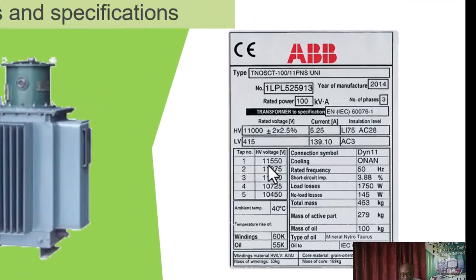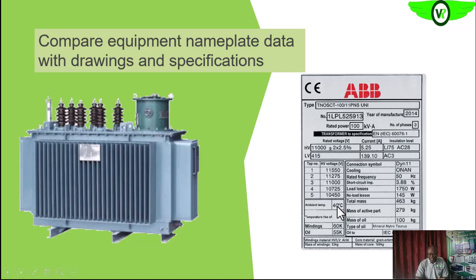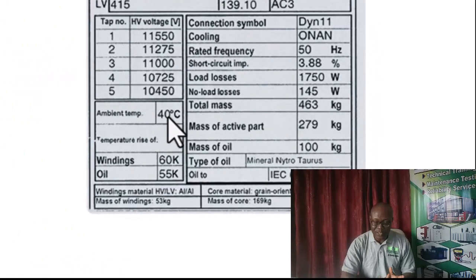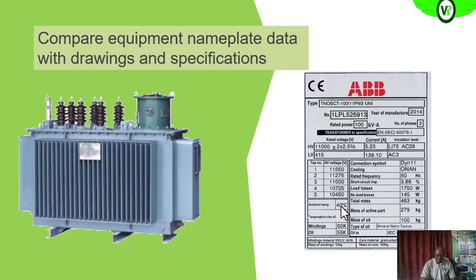Basically, we'll look at the input voltage, that is the high voltage side, and then the output voltage. If it matches what was requested, fine. And then the power rating; those are some of the things that we look at. For the ambient temperature, which indicates the maximum temperature of the environment in which the transformer can operate, we check that it matches the ambient temperature expected in the area where we are installing the transformer in our facility. All of those we are to check to see that it meets specification.